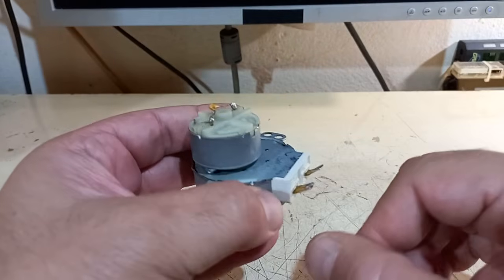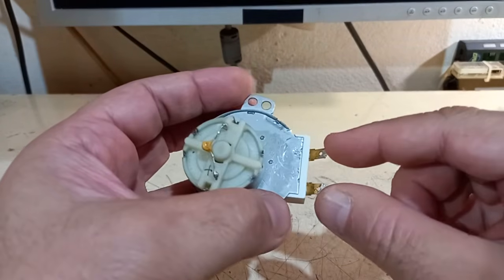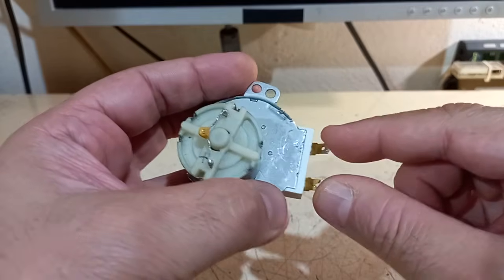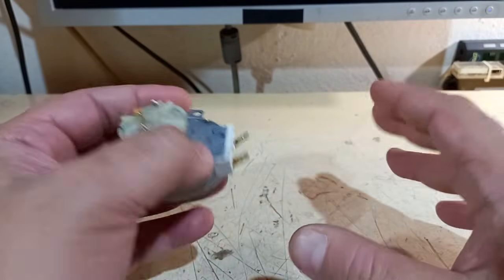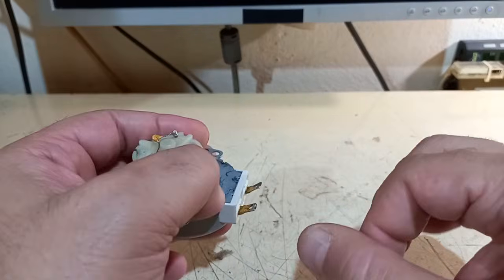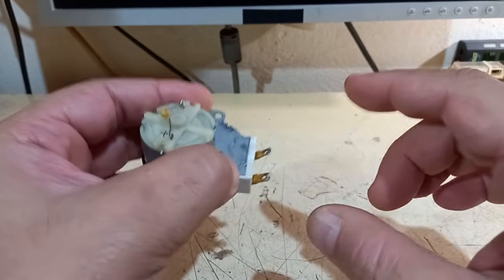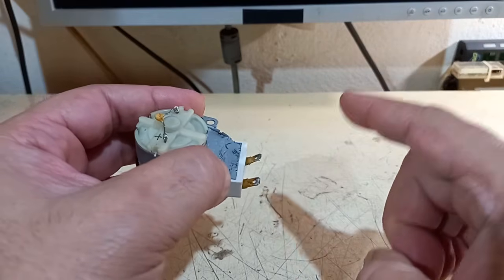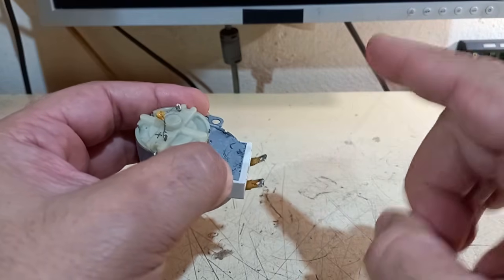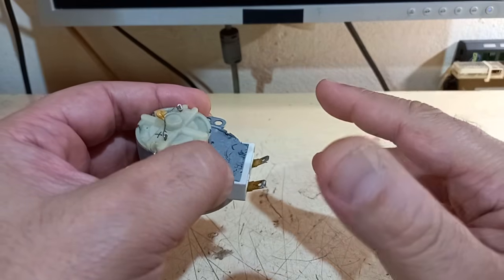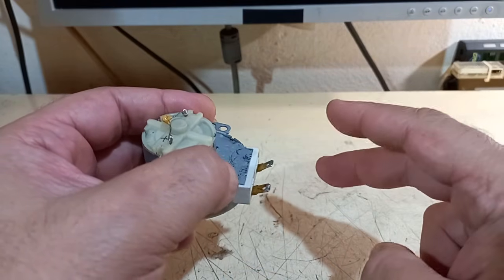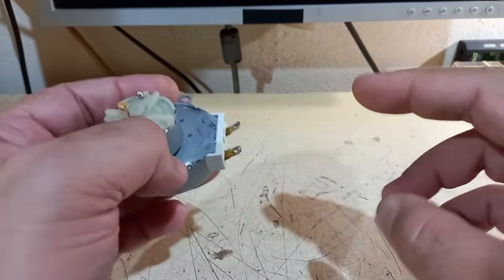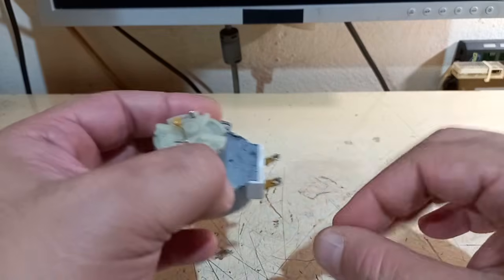Another side note: there are not only the ones that run at 115 volts AC, there's also apparently a type that runs at, if I remember correctly, 36 volts AC, powered from a winding on the fan motor of the oven. So if the fan motor has 3 contacts instead of 2, two of those contacts go to this synchronous motor here, which acts as an auto transformer, a step-down transformer, and runs at a much lower voltage — so you're warned.